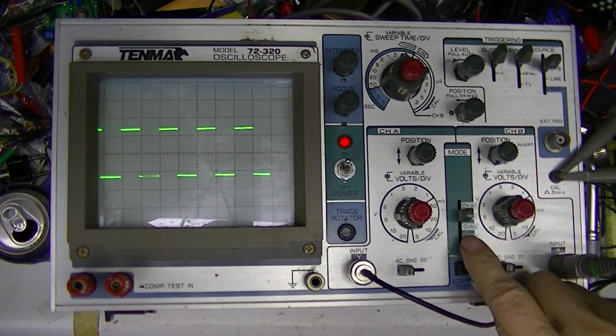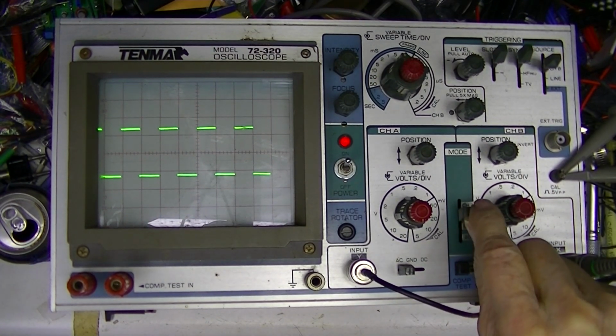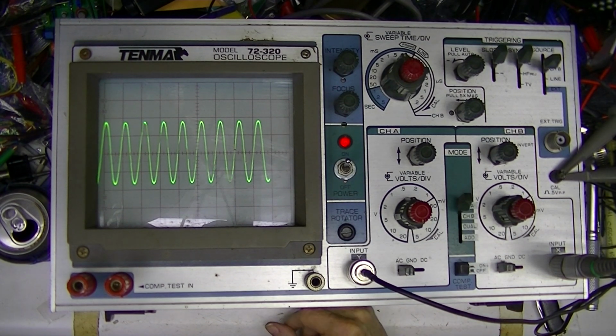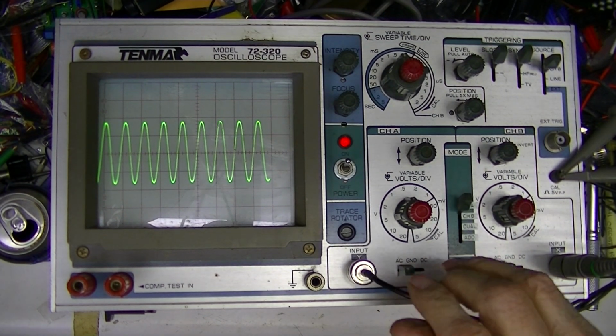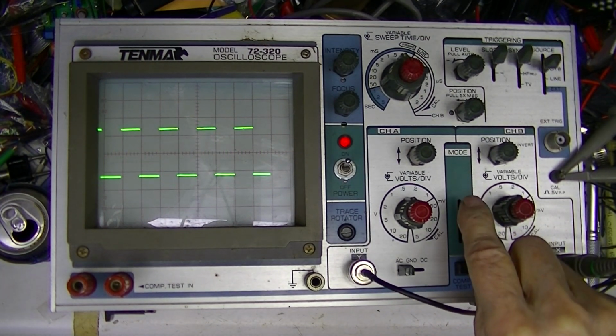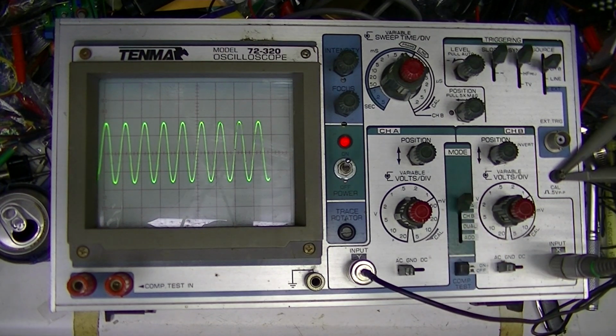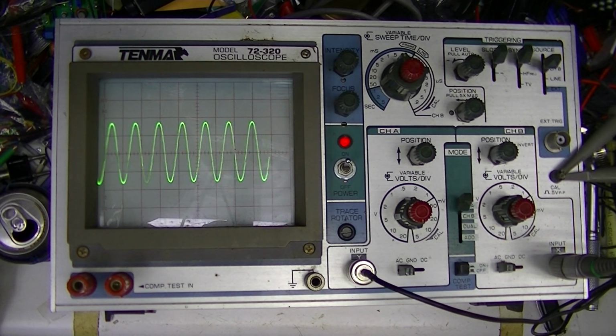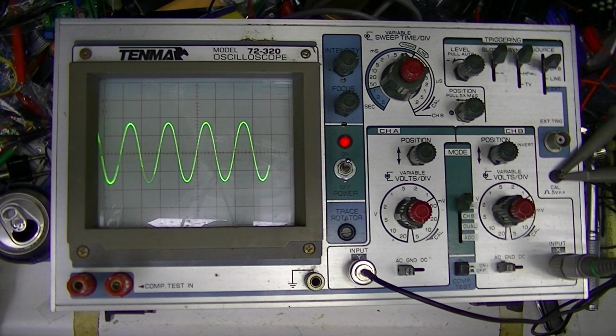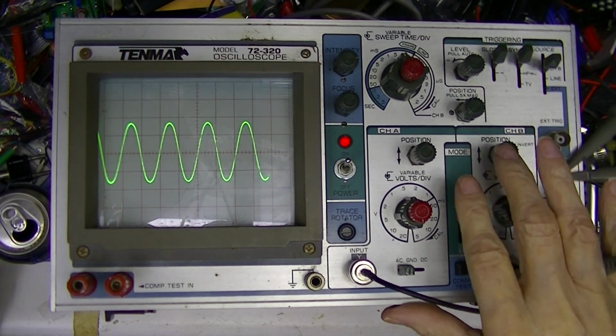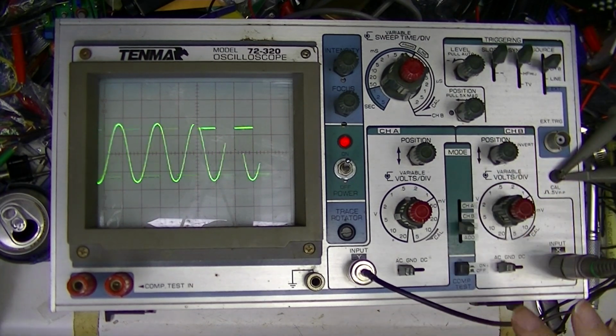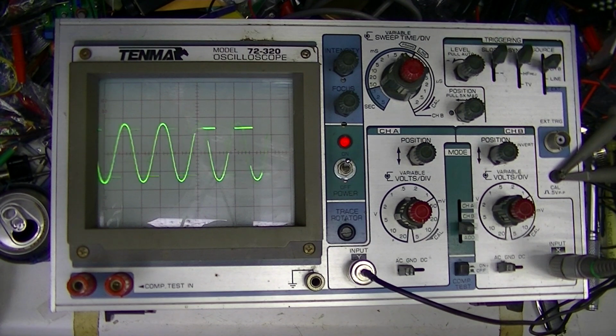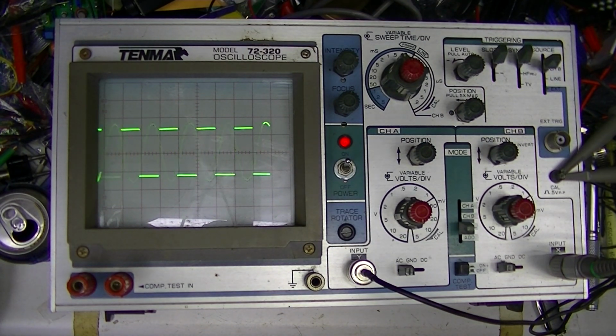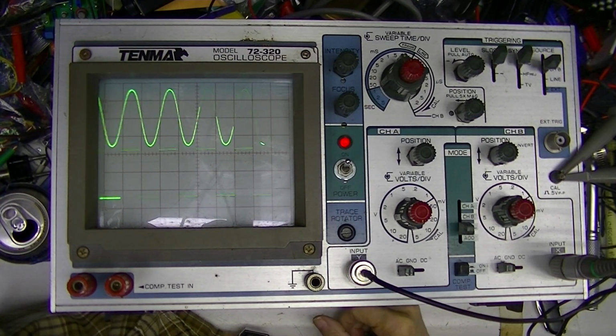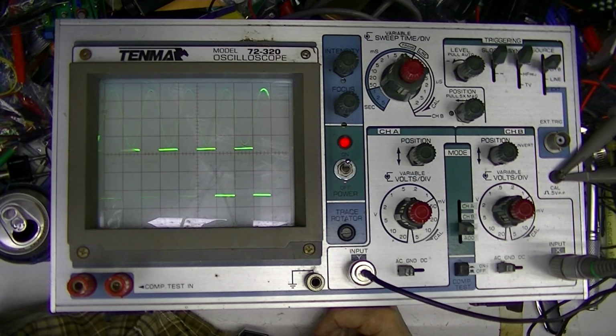Now I'm on channel B because you can see I put the switch in the channel B position. Channel A is on the sine wave, which is coming from my signal generator. Move the signal generator to 1000 Hertz. And I'll display both of them, which is in the dual mode. My signal generator is not too accurate. That's pretty close though. I'll try to find a manual for this. If it's not in the box already, I'll try to find it.